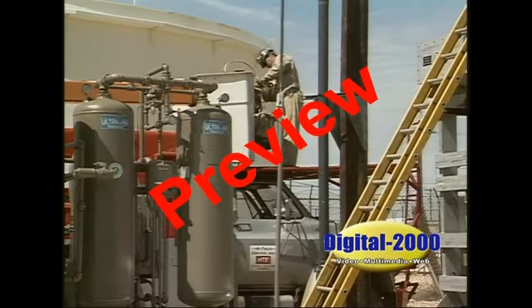The marking must be clearly visible to qualified persons before they examine, adjust, service, or perform maintenance on the equipment. The NFPA 70E requirements also ensure a qualified employee is present wherever there is a potential for arc flash. Overall, these requirements are intended to reduce the instances of serious injury or death resulting from arc flash. The information on the field label should warn employees and other workers that a serious hazard exists and appropriate work practices and PPE should be used.